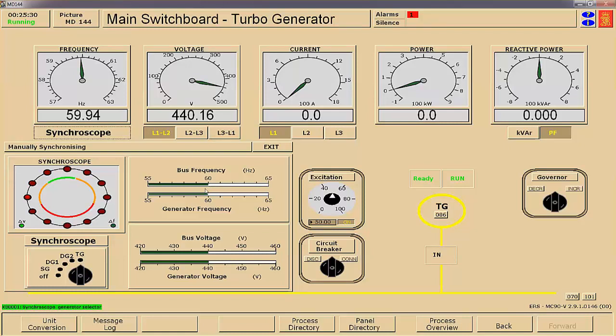Here you have bus and generator frequency. Your generator frequency needs to be above bus, and you should have 2 to 5 volts on the generator higher than bus. Excitation controls voltage. The governor controls speed. Now, if anything, we're going backwards on our synchroscopes, so I'm going to increase this until I am moving in the clockwise direction at a fair rate.